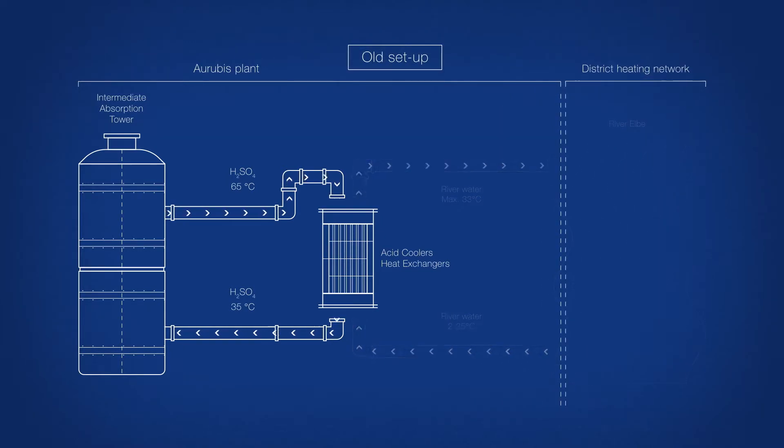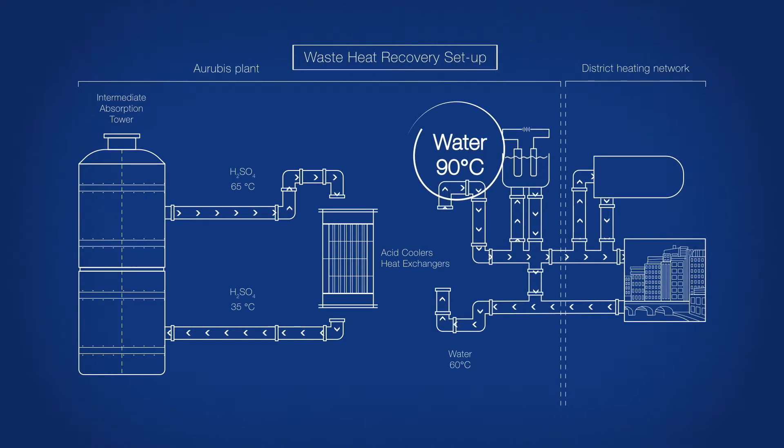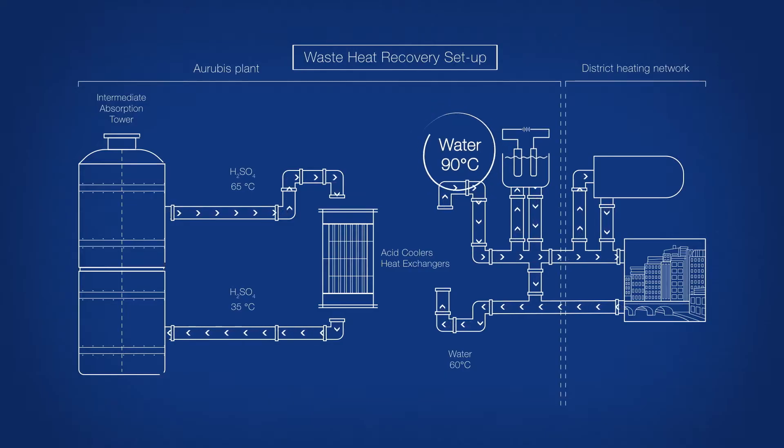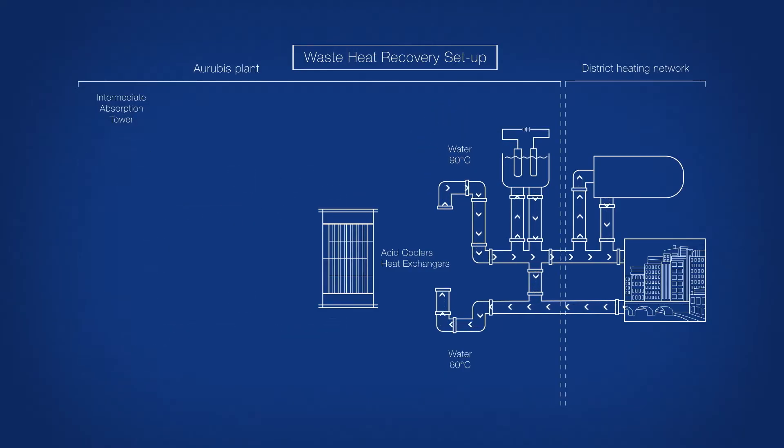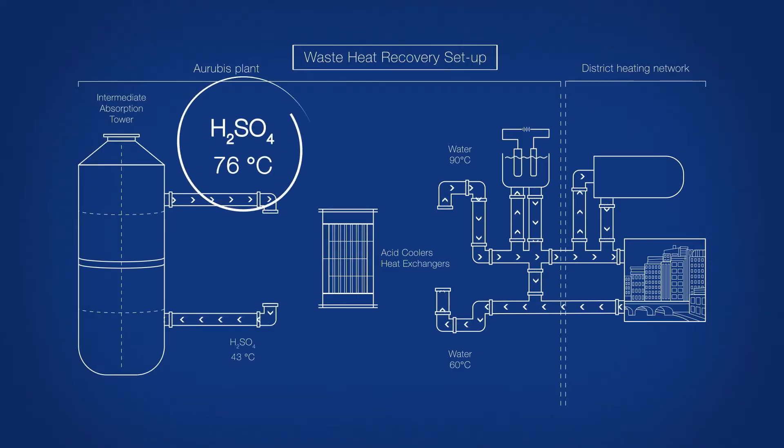One challenge was that the hot water used in district heating needed a temperature of at least 90 degrees Celsius. To achieve this, Aurubis had to redesign the heating source, increasing the process temperature of the sulfuric acid to approximately 120 degrees Celsius.